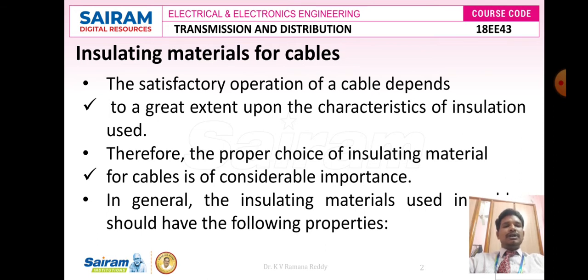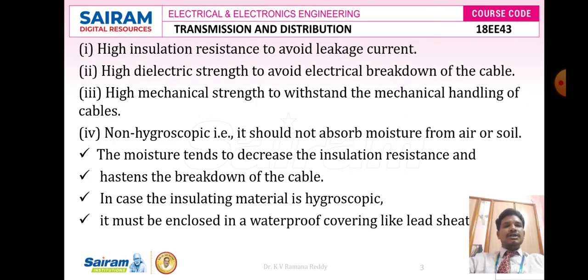In general, the insulating materials used in underground cables should have the following properties: high insulation resistance to avoid leakage current and to avoid electron pockets via treeing, tracking, and voids. High dielectric strength to avoid electrical breakdown of the cable. High mechanical strength to withstand mechanical handling of cables, especially to avoid mechanical injuries and mechanical stress.